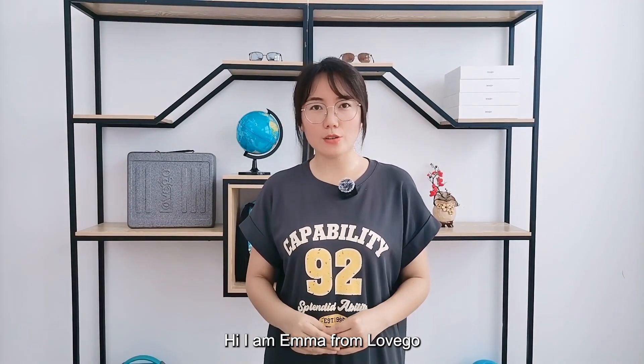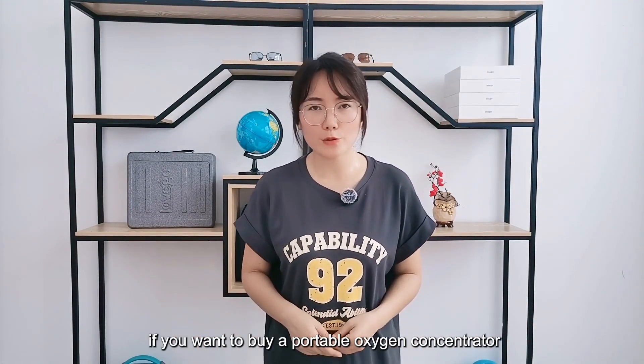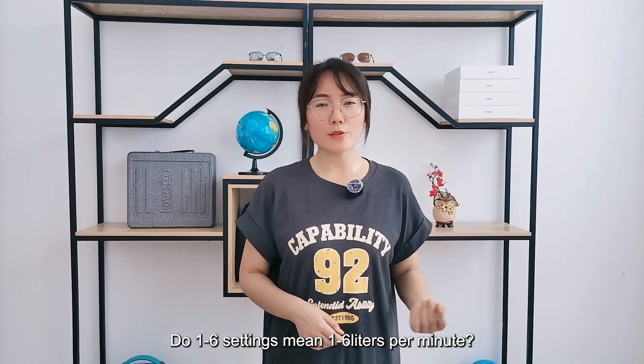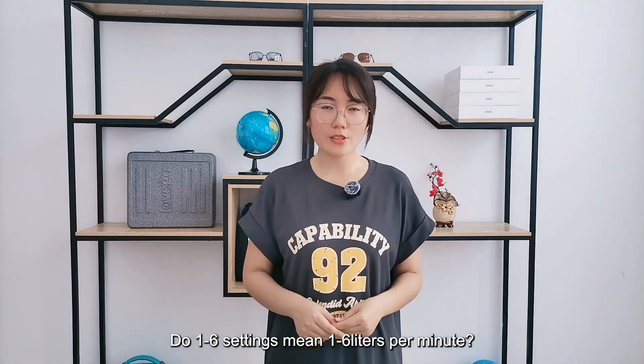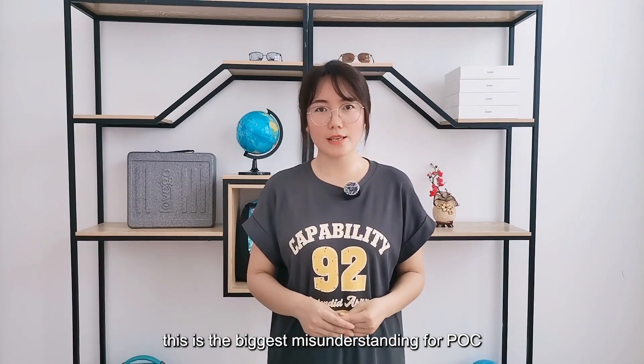Hi, I'm Emma from Lovego. Flow settings 1 to 6 may be confusing if you want to buy a portable oxygen concentrator. Do flow settings 1 to 6 mean 1 to 6 liters per minute? Of course not. This is the biggest misunderstanding about POCs.